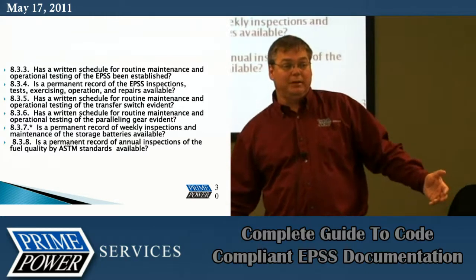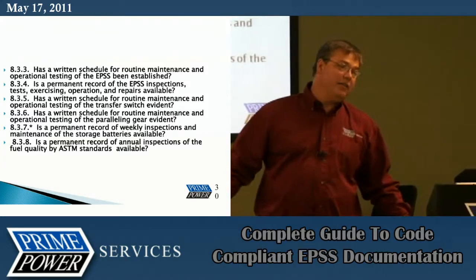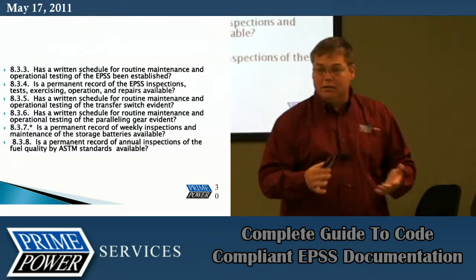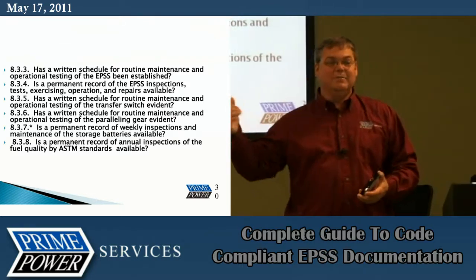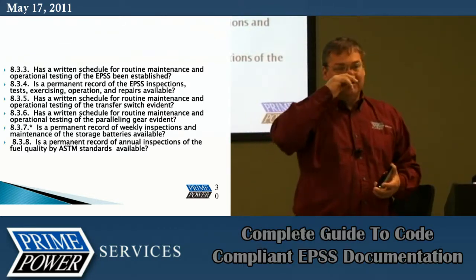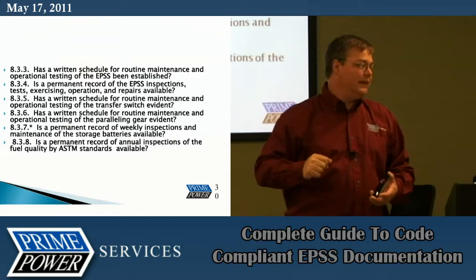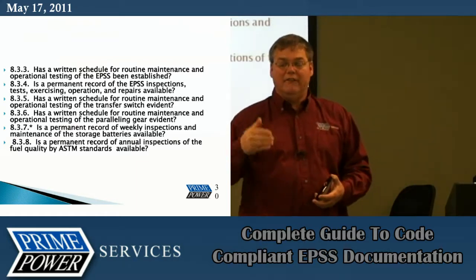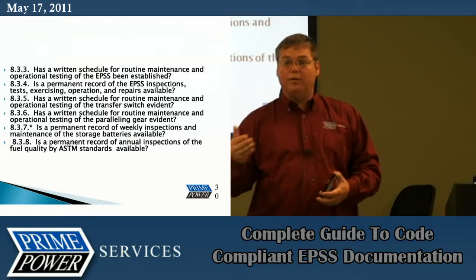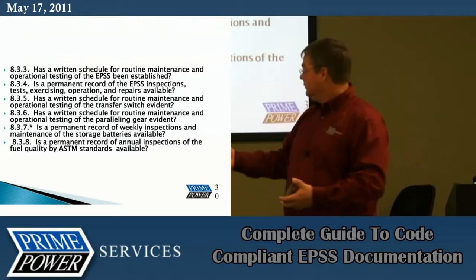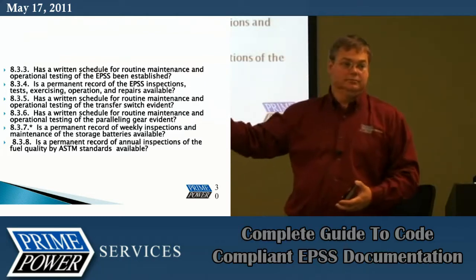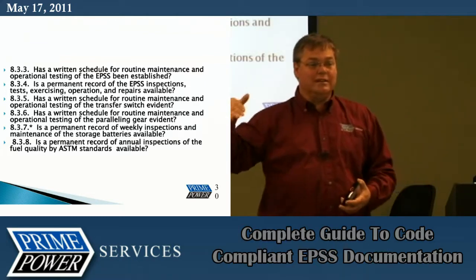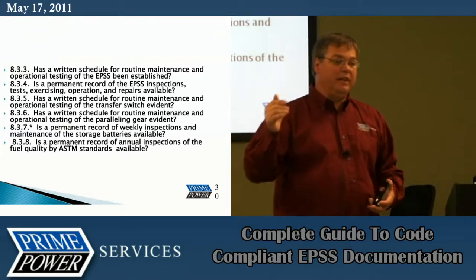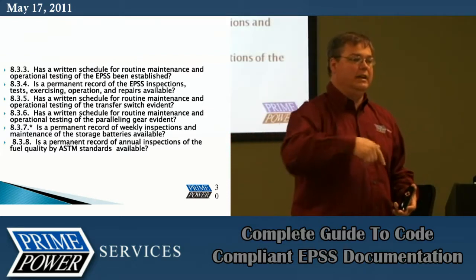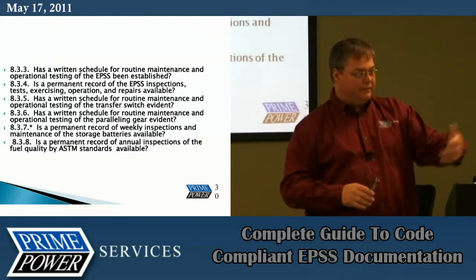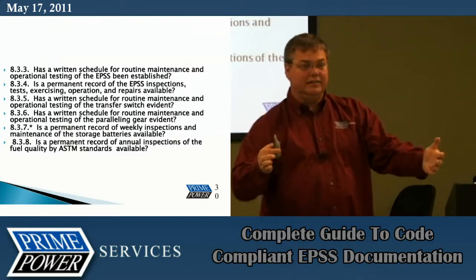Now, if you're running through and replacing that fuel, you only got a 500-gallon tank, you're using 700 gallons a year, then there's not much you need because the fuel is less than a year old. So again, you have to run that risk analysis yourself to determine. If you keep fuel in your tank for over a year, you need to run that test. All right? The only way that you could not get that is if you could show that it got filled up less than a year every time, and then have the date of the fill when it was done and say that it's not a year old.